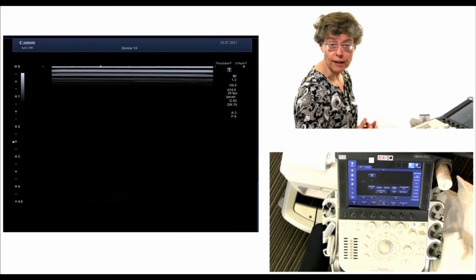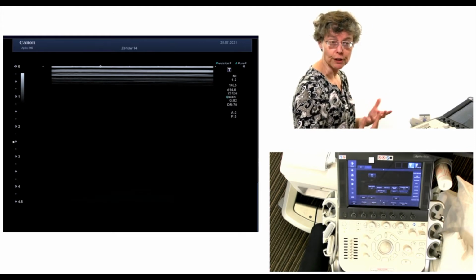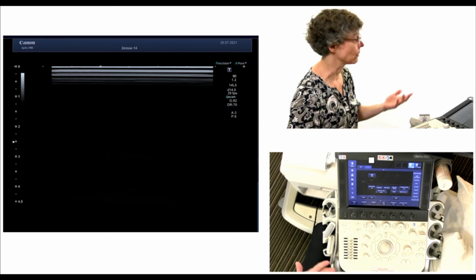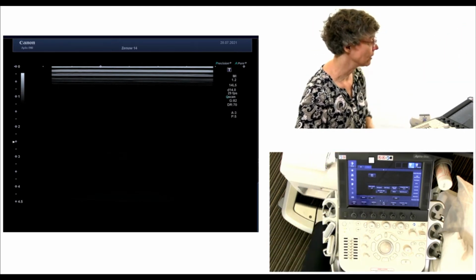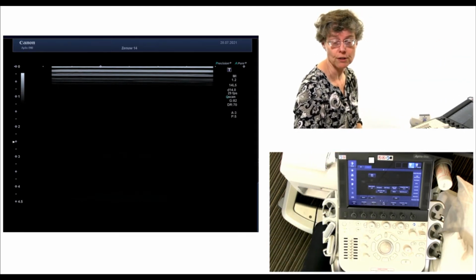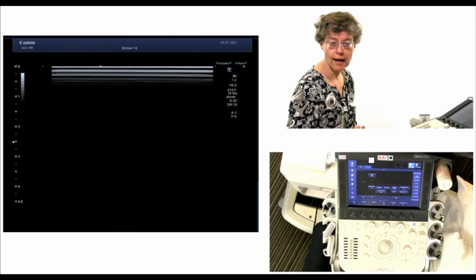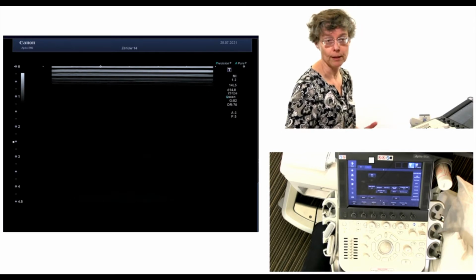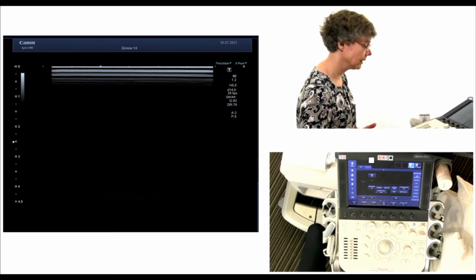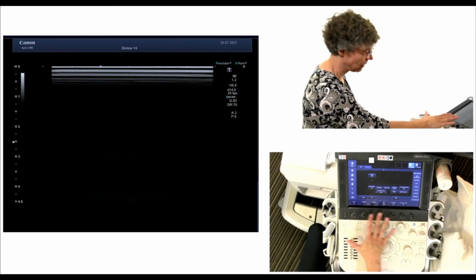Now you can see a preset will contain some things you've pre-configured to come up every time you touch that button. So in this case the screen has a standard depth of 4.5 centimeters. If you are scanning a person who is much larger than that, maybe because their BMI is very high, you might want to adjust it.